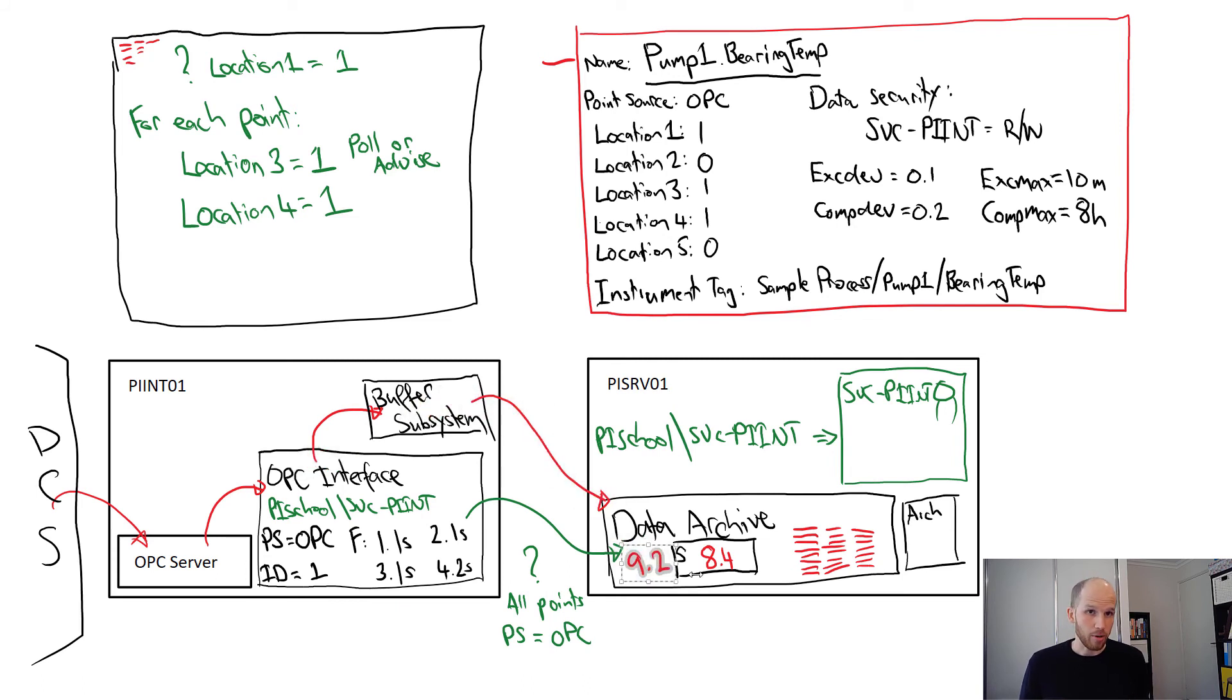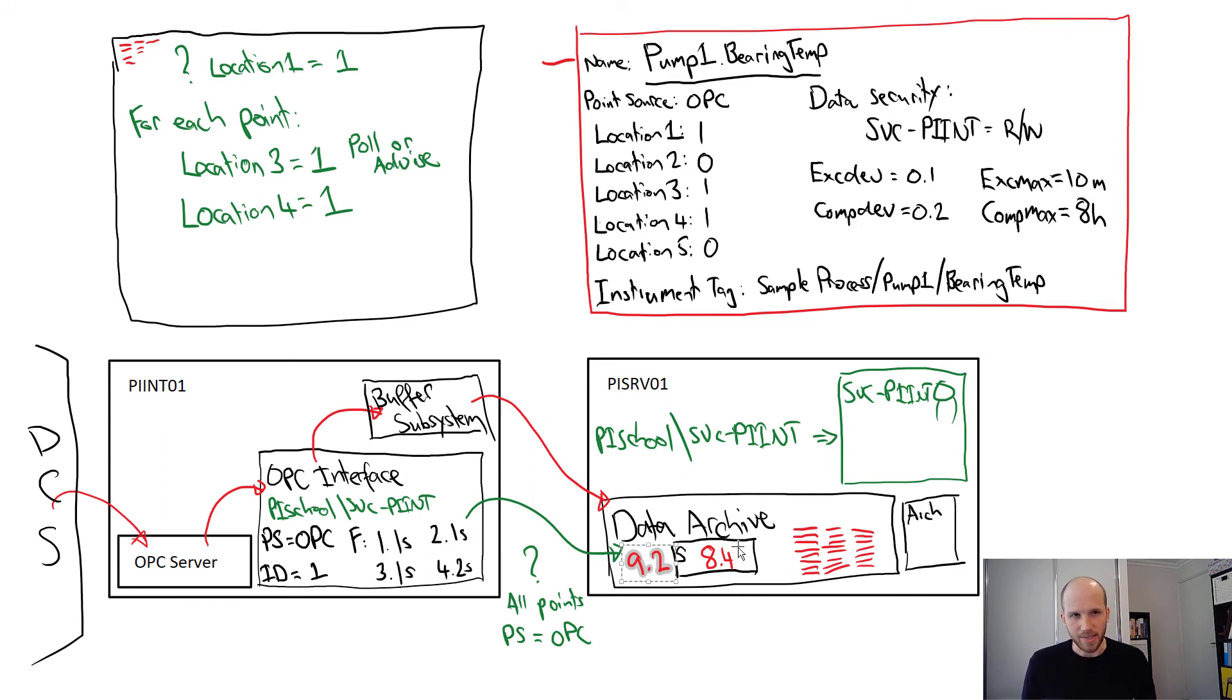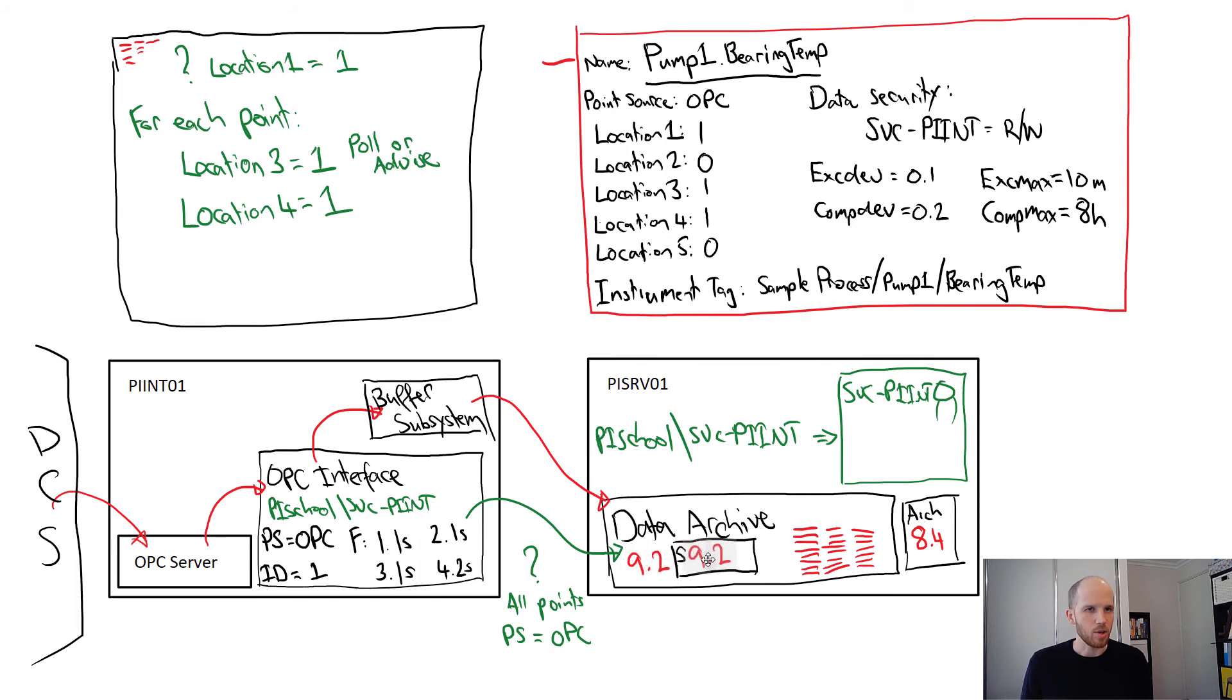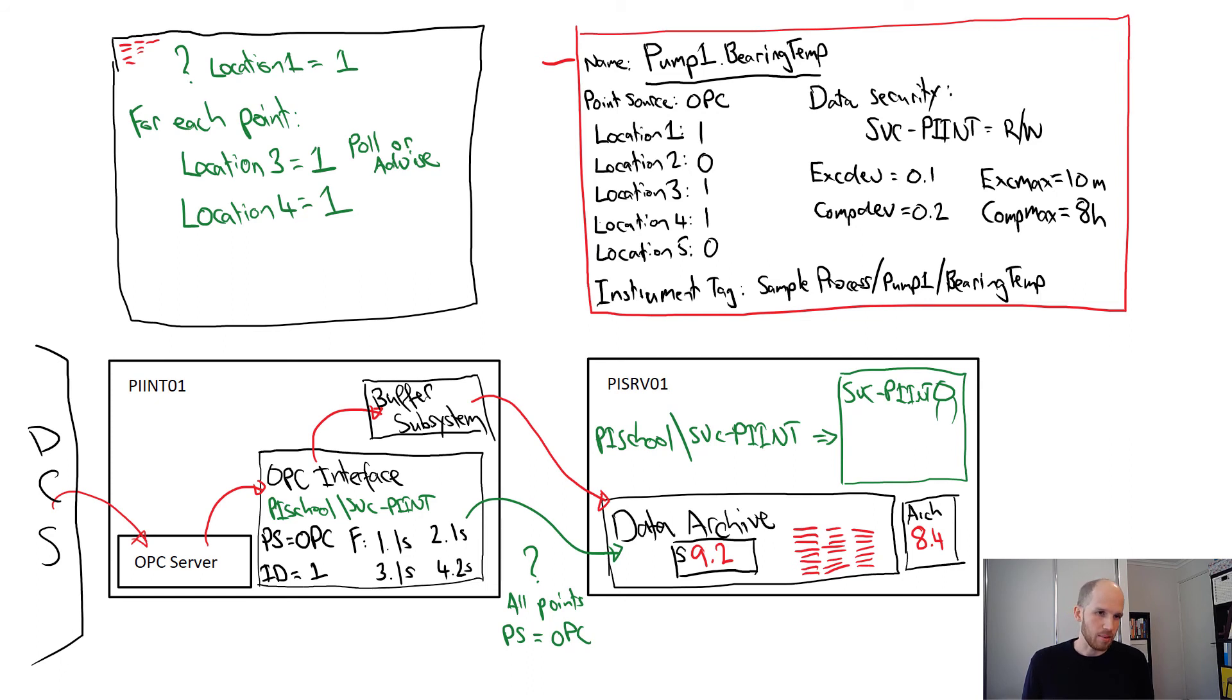The old 8.4 value in the snapshot gets tested using another test called compression. If it passes the test, it gets stored in an archive value ready for historical queries and reports. The new 9.2 value replaces the old value in the snapshot. This is the most up-to-date value the data archive has now, and it'll automatically be fed through to users with active trends open.